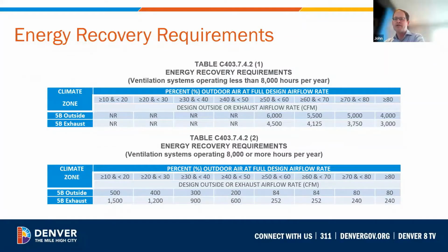Energy recovery systems must meet minimum efficacy requirements. Many systems have a bypass damper to reduce the system pressure drop when free cooling conditions allow. So that would allow you to bypass the energy recovery device for a lower pressure drop when you can simply have free cooling and do not need the energy recovery during mild outside air conditions.